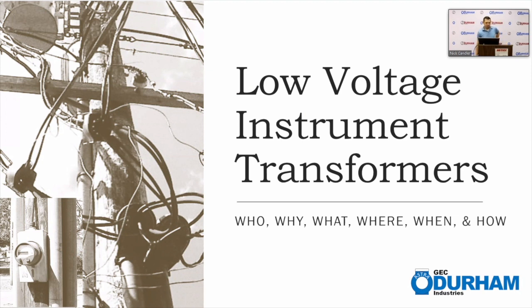So let's jump right into this in the interest of time, and we want to get to that high accuracy CT demo here at the end. So you have joined a presentation on low voltage instrument transformers, the who, why, what, where, when, and how of low voltage instrument transformers, not to be confused with distribution transformers, medium voltage transformers, medium voltage instrument transformers. We're talking about 600 volt class revenue metering instrument transformers.